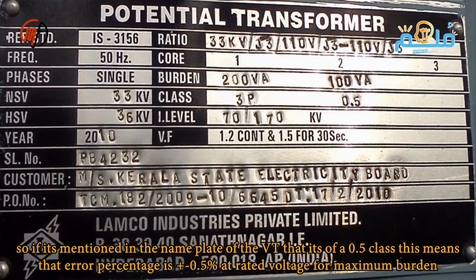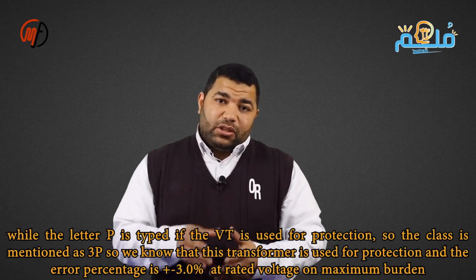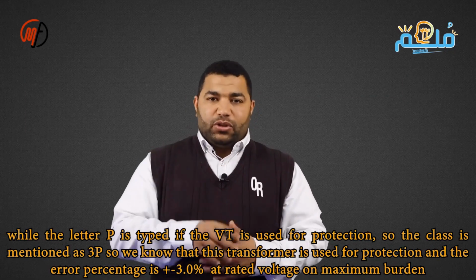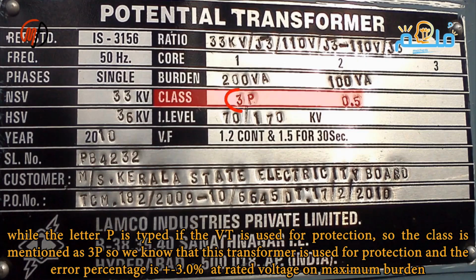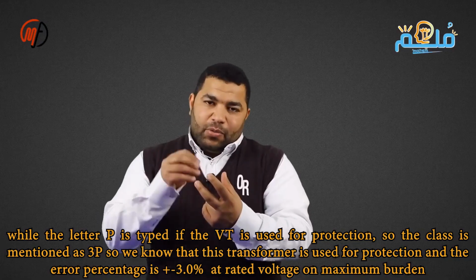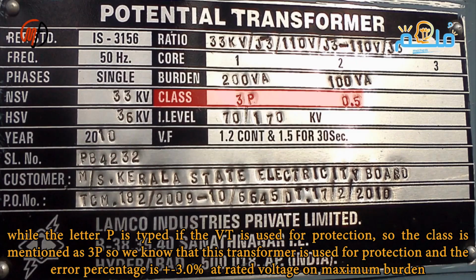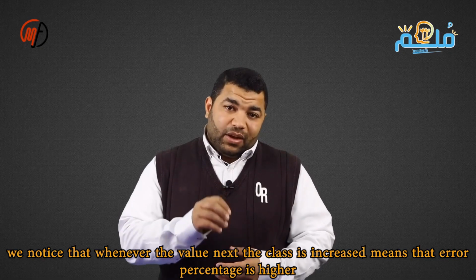Voltage transformers differ from power transformers. Both work on the same principle, but voltage transformers have capacities in tens of volt amperes, while power transformers exceed 300 megavolt amperes. When the letter P is mentioned, indicating this transformer is for protection, it's noted as class 3P, and the error ratio is plus or minus 3% of the rated voltage at the highest burden. We notice the higher the value next to the class, the higher the expected error ratio.